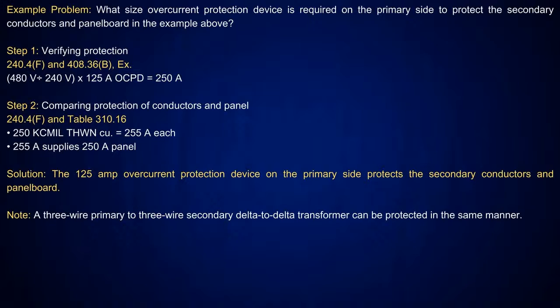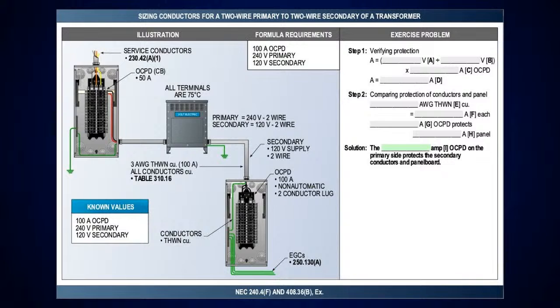So if I had 250 amps, what's the next size above that? That's 255 amps in Table 310.16 in the 75 degrees C column, which would have required a 250 kcmil conductor to supply that panel board. Okay? Is 225 a standard size? Or 255? No, that's for the conductor amperage. Oh, gotcha. Okay, so it's 250.